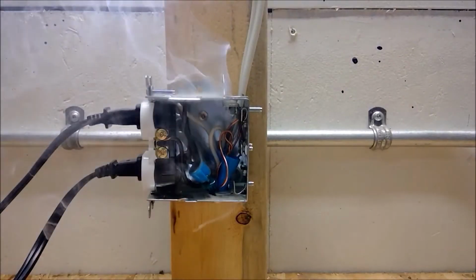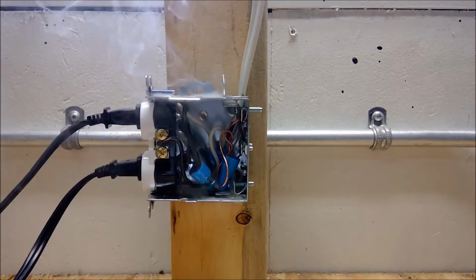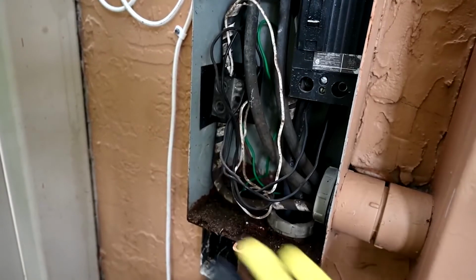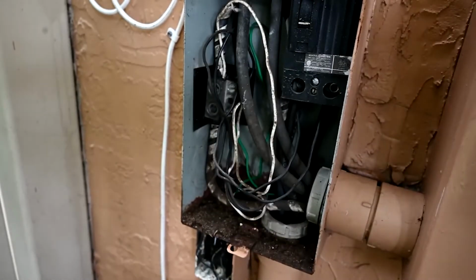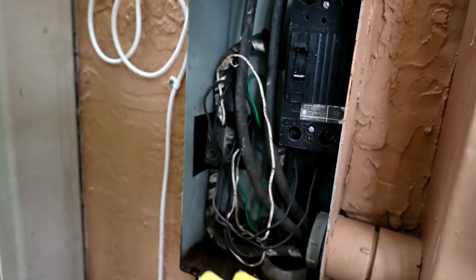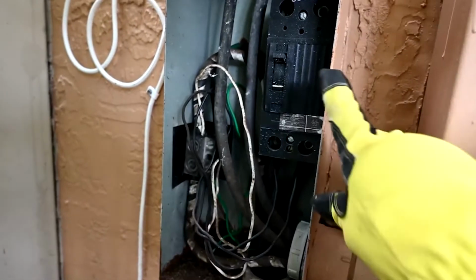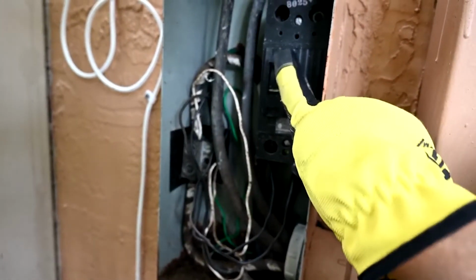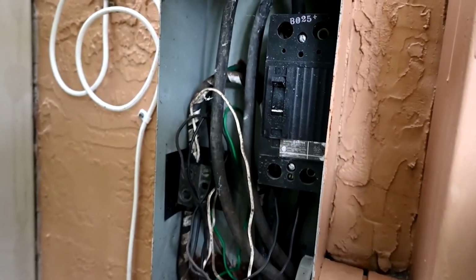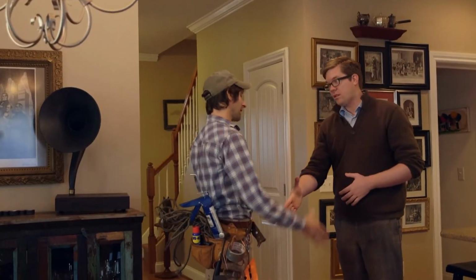When the wiring and circuit breakers can't handle the electrical pull of the equipment put into their circuit, it's called excess wiring load. Circuit breakers that continuously trip when anomalies in the current are detected are usually the first indicator of this problem. If you find that the electrical system is forced to carry greater load than it can handle for an extended period of time, electrical components will wear out much sooner than they should. This is a problem that can happen at any moment and even to the most seasoned electricians. Additionally, it can cause a lot of damage.